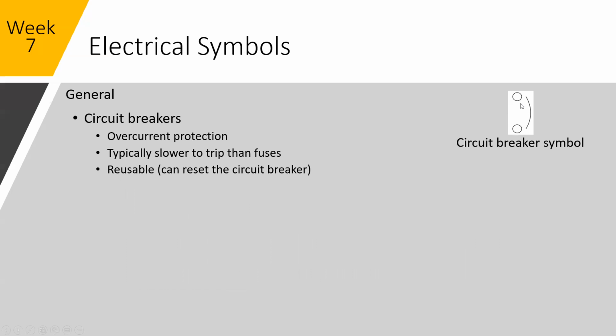We'll have circuit breakers. So here, because there's no tube between the center, you know that this is a circuit breaker. They're also overcurrent protection. They typically take longer to open, and by longer, I mean like fractions of a second. You can get some fuses that'll blow in milliseconds, and a circuit breaker could take 100 milliseconds to trip. And sometimes that difference is enough to protect or burn out your very expensive piece of equipment later on down the circuit. Again, typically slower than fuses, but circuit breakers are resettable unless they are hit with a voltage so much higher than they're rated for that they just blow up, fuse open or fuse shut. But they're very convenient. Most houses nowadays have circuit breakers. The idea behind them for electrical control panels is identical.